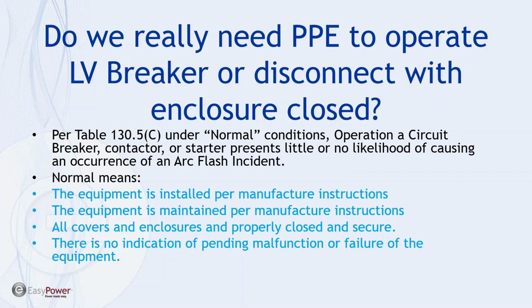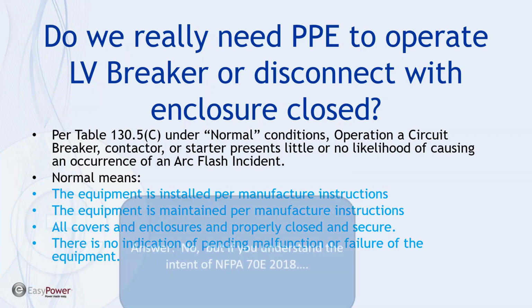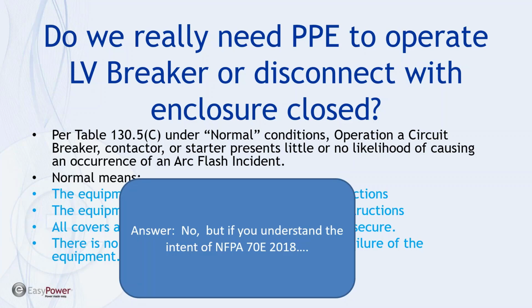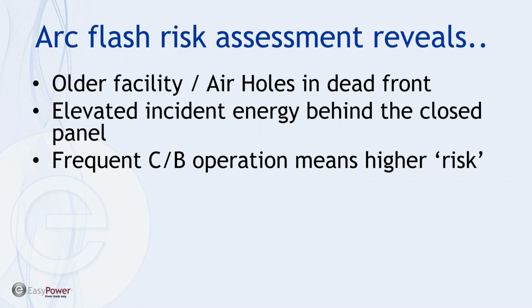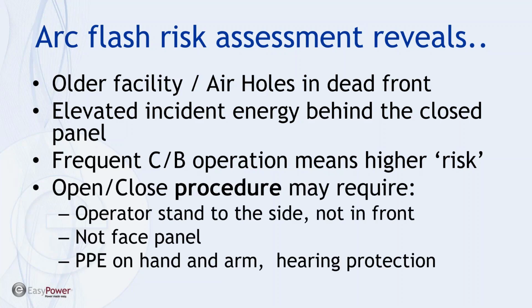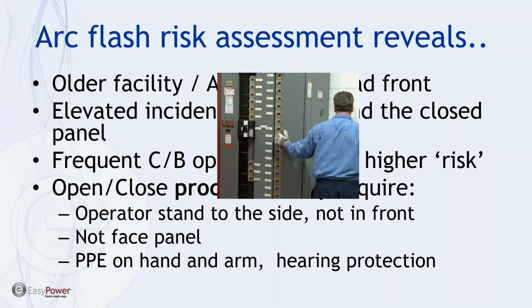However, if we really understand the intent of the 2018 version of 70E, we may approach the following situation a little differently. We've done an arc flash assessment on our plant, and we realize in our older facility that there are some buses that may be suspect as far as their integrity, may have air holes in the dead front, we may have elevated energy behind the closed panel, and yet we still require an operator to frequently manipulate, close or operate a breaker. And so we may come up with a procedure, based upon our knowledge now of our system, that may require an operator to stand to the side and not in front of the panel or face the panel, have additional PPE on their hand and arm, maybe some hearing protection, and we need to ensure that the operator understands why this is important as far as safety.